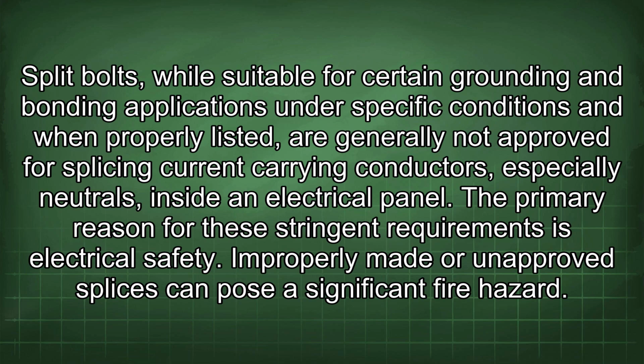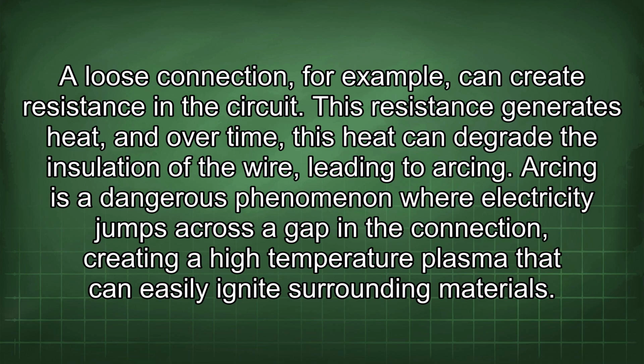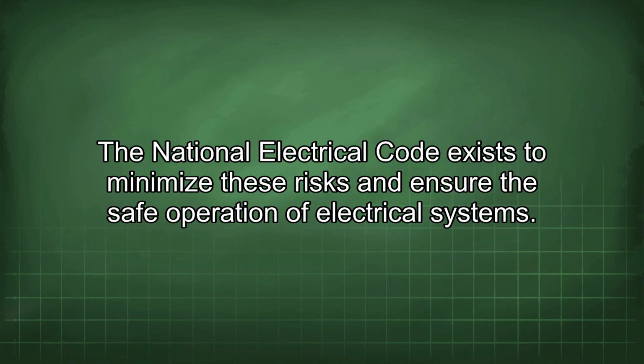The primary reason for these stringent requirements is electrical safety. Improperly made or unapproved splices can pose a significant fire hazard. A loose connection, for example, can create resistance in the circuit. This resistance generates heat, and over time, this heat can degrade the insulation of the wire, leading to arcing. Arcing is a dangerous phenomenon where electricity jumps across a gap in the connection, creating a high-temperature plasma that can easily ignite surrounding materials.